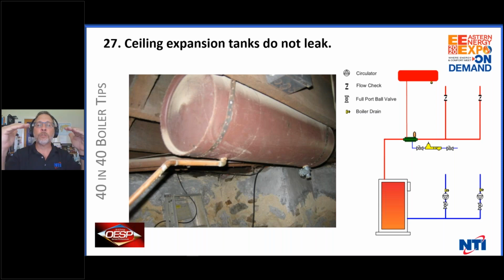But when the water cools in that tank, the colder a liquid is, the more soluble gas is in that liquid, which means that when that water chills in that tank, it absorbs some of the air in that tank. So as the cold water is coming down and the hot water is going up, the cold water comes down to the system, the boiler heats it, air goes out of the system, but nothing's there to put the air back into the tank. Yes, ceiling tanks don't leak. I'm not saying it's a bad idea to put in an Amtrol tank, but ceiling tanks rarely leak.